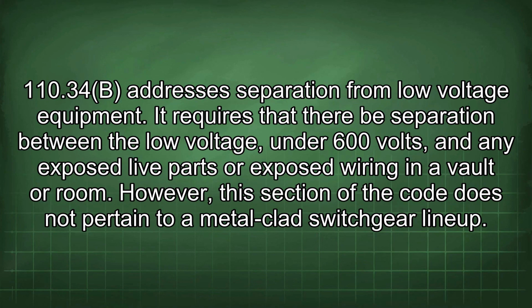110.34b addresses separation from low-voltage equipment. It requires that there be separation between the low voltage, under 600 volts, and any exposed live parts or exposed wiring in a vault or room. However, this section of the code does not pertain to a metal-clad switchgear lineup.